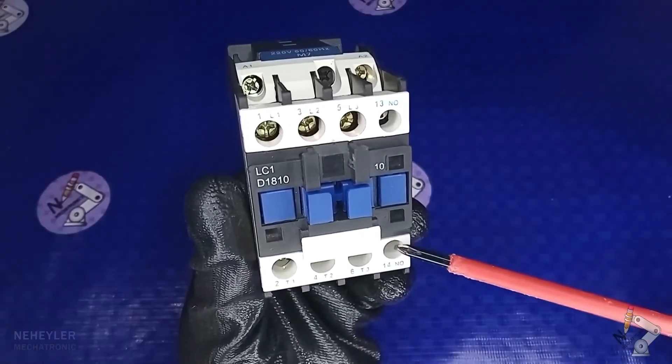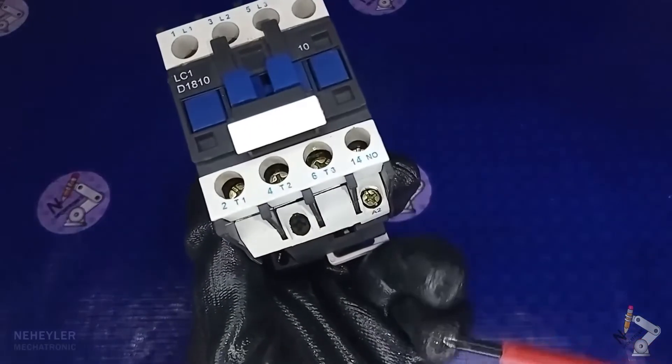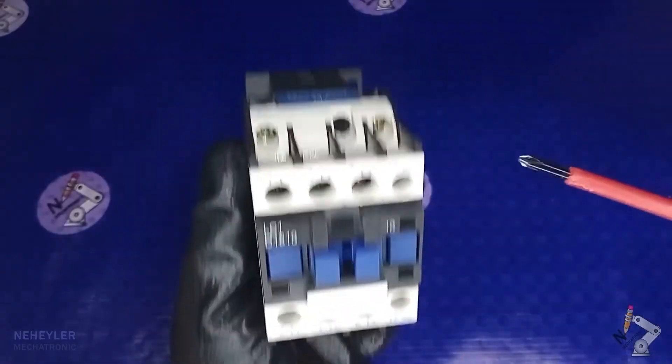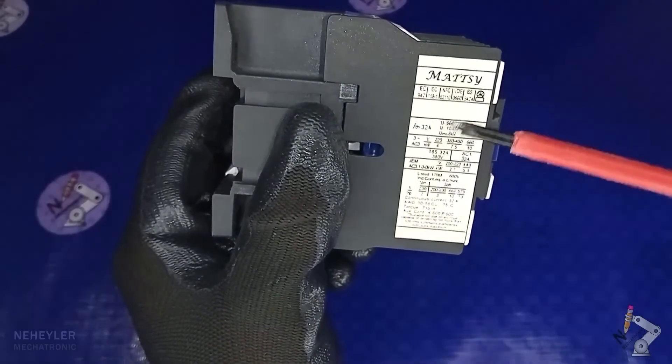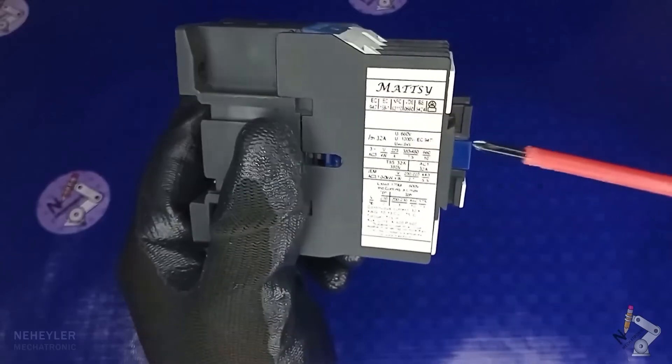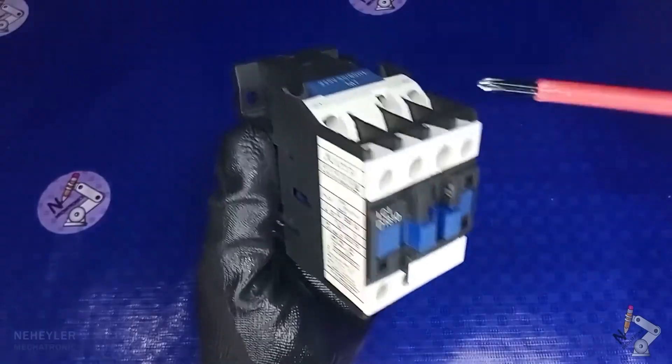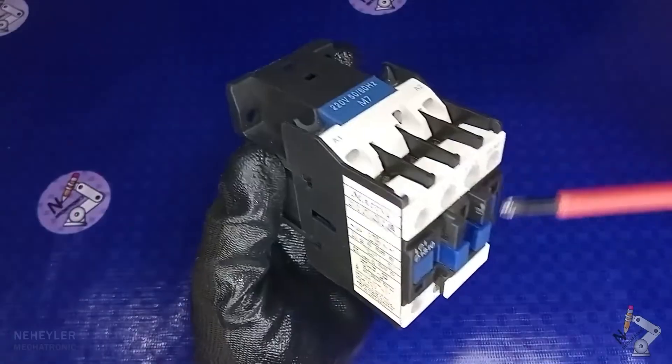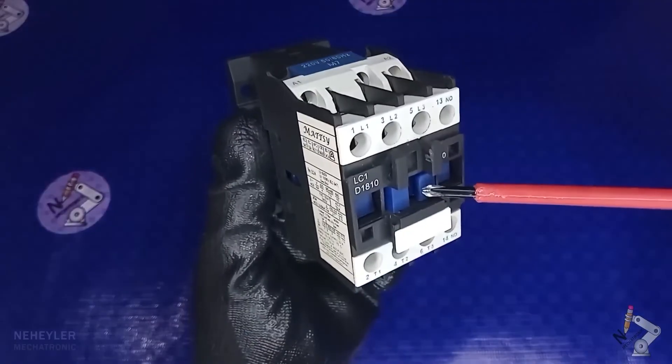While terminals 13 and 14 are part of a normally open auxiliary contact. At the bottom we have terminal A2, which is the same as the one up here. Here they give us a table with specifications of current, voltage, power and more additional data that will be explained in more detail later. When the coil is energized through terminals A1 and A2, this moving part retracts, allowing all contacts to be closed or bridged.